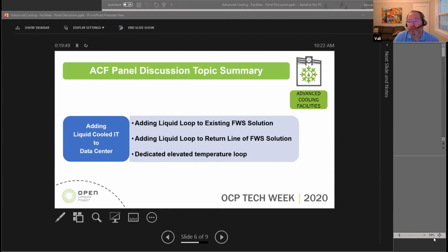And W5 goes even above that 45 so that you can use facility water to reheat other or sell your heat to other users. So the W classification is a good rule of thumb. It's actually in the process of being modified right now because it's too granular a view on the availability of water. So instead of having, let's say, W3, W4, which has a pretty big step between them, it may actually go to W32 or W40, and then the next one, which would be the W5 range above that.